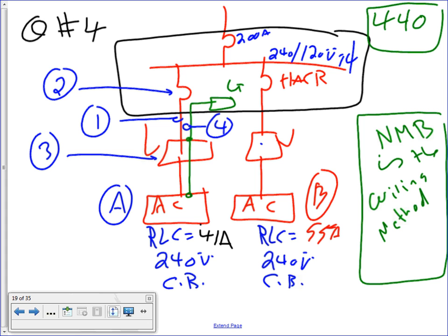We need to size the overcurrent protection device. We need to size the conductor. We need to size the disconnect. And I need to size the equipment ground conductor. Same thing, I'm still using that worst cable that God created, which is NM cable. My article is 440. Cool. Again, this will be a PDF. You guys have a copy of them before, and you will have them on the network. So don't sweat it too hard. You don't have to sit there and sketch that one. It'll take you half an hour.